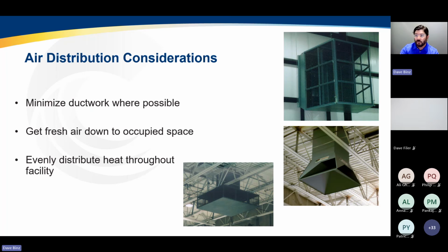And depending on what the building needs, where that exhaust is, we have a variety of ways that you might want to deliver that air through higher velocity distribution, lower velocity types of plenums, but ultimately look at what the building is going to give you and how you want to distribute the air on a large volume perspective, just to make sure we're getting that ventilation in at the right space and not trying to have pockets of high temperatures or warm or cold spots. So again, a variety of systems in the industrial application, but get what the building gives you, solve your ventilation problem first, and then provide some unique control options, modulation options, or ductwork to make that overall system match their operations.